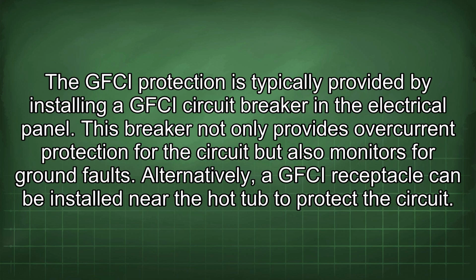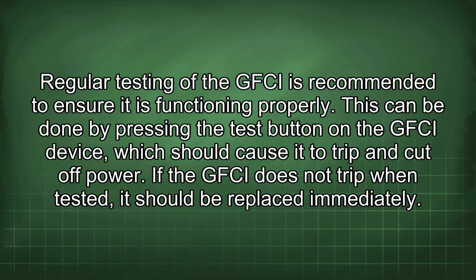The GFCI protection is typically provided by installing a GFCI circuit breaker in the electrical panel. This breaker not only provides overcurrent protection for the circuit but also monitors for ground faults. Alternatively, a GFCI receptacle can be installed near the hot tub to protect the circuit. Regular testing of the GFCI is recommended to ensure it is functioning properly. This can be done by pressing the test button on the GFCI device, which should cause it to trip and cut off power. If the GFCI does not trip when tested, it should be replaced immediately.